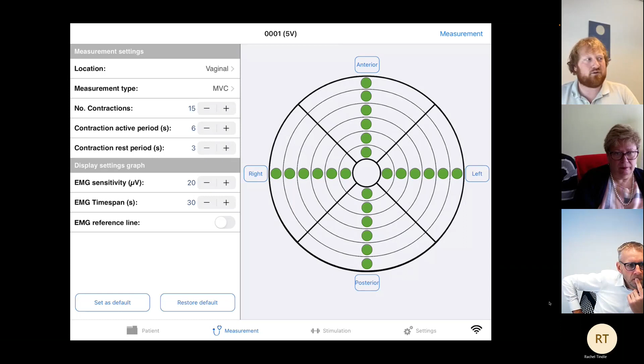The type of measurement I would like to perform, so a rest measurement, MVC measurement, or an endurance measurement. I can also perform a training, but that is not stored in the history tab. Then if it's a rest measurement, I can set the total duration, so 1 minute, 2 minutes, 3 minutes, you name it. If it is an MVC or endurance measurement, so where you want to have contractions, you can select the amount of contractions you would like to perform, and then the active period and the rest period in which you would like to see the contractions.